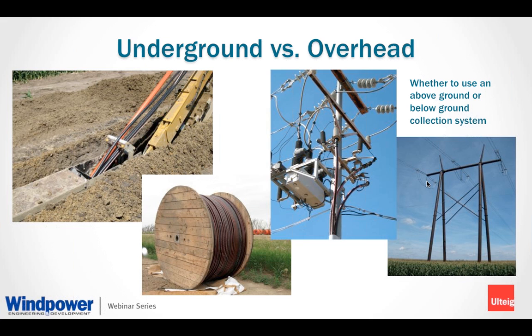Although the overhead can offer a cheaper installed cost over really long distances, you're still going to need underground to connect to each turbine. Overhead also has issues with landowners because they sometimes don't like these structures on their properties. Overhead also presents more logistical problems like construction crane paths, operation maintenance problems from animals or environment. With overhead, you still have issues with storms when they come through and can knock out the power lines. This can sometimes be easily seen by someone visually inspecting them, versus if there's an underground failure, they would have to excavate and find the problem with other means.